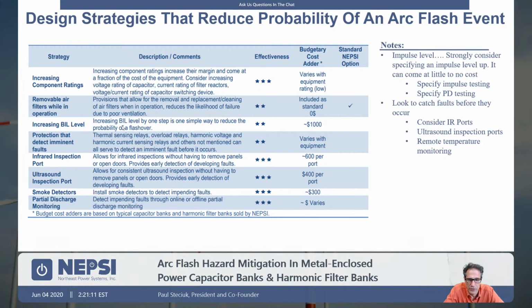Increasing BIL is also something to think about. To go from a 95 kV BIL system on a 13.8 kV system to 110 or to 125 comes at the fraction of a cost. So again, increasing BIL means to increase the spacing. It means to increase the height of the insulators. It means to reduce the probability of a fault from occurring in the first place.